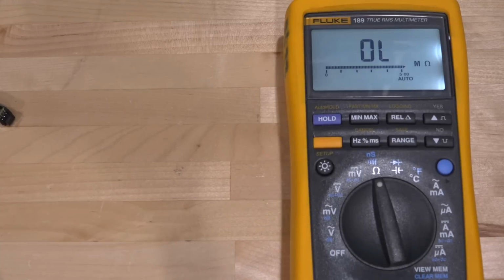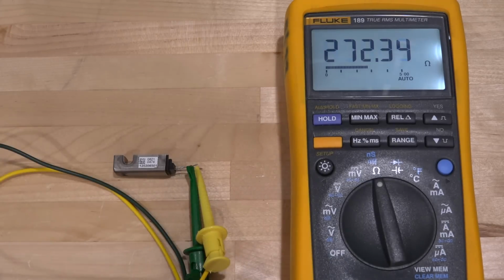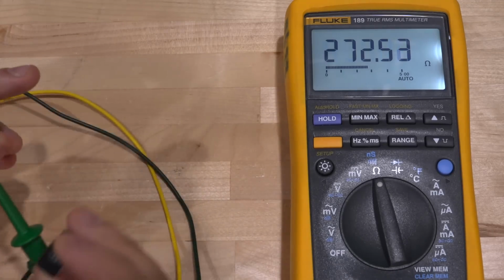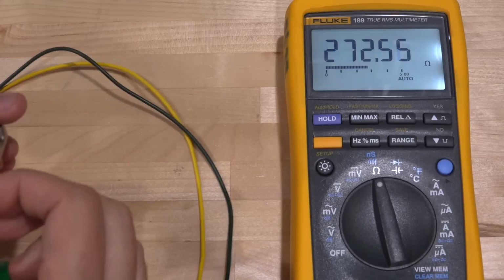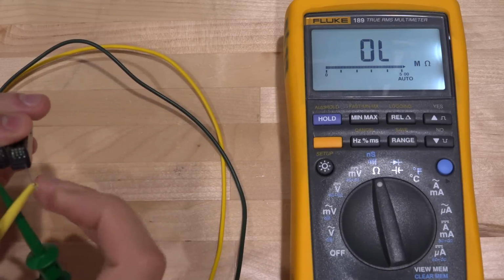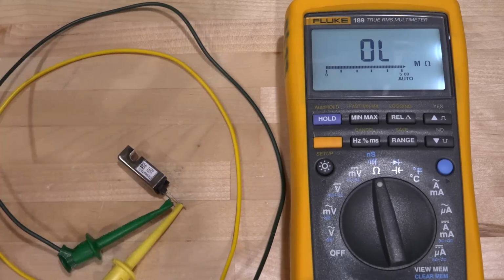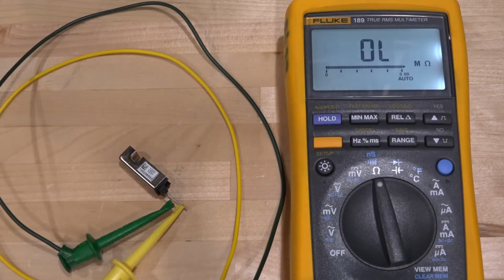So that's a good sign. The next thing we need to check is whether the resistances of the Hall effect sensor are the same. So here are two of the terminals of the Hall effect sensor on the working transformer, and I think these are the power ports. We're seeing about 272 ohms, which I think is normal. I don't know what kind of Hall effect sensor they're using, but that doesn't seem like an unusual value. Now we can switch it over to the non-working one. Let's put it down, and we get nothing. Okay, so right off the bat, there is definitely a problem. It looks like there's a disconnection, or maybe the Hall effect sensor is dead, but it's likely that it is disconnected because the resistance is in the tens of megaohms or higher. We can't even measure it.